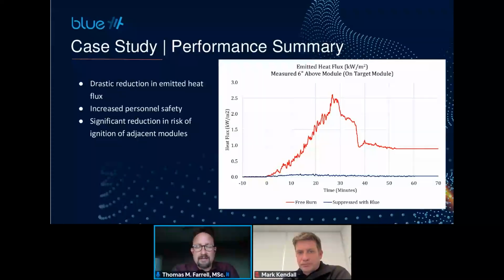For the free burn test, you can see in this data, we got up to a peak value of about 2.5 kilowatts per square meter. And that means that we were above the 1.3 kilowatts per square meter for about 25 minutes, which means this is an unoccupiable space. And this particular one was mounted about 6 inches above the module. We also had gauges set about 3 meters away to the side and about 3 meters away directly in front of the vent. And the one directly in front of the vent got so hot that it was actually destroyed during that free burn test. So being in an occupied space there is a bad thing.